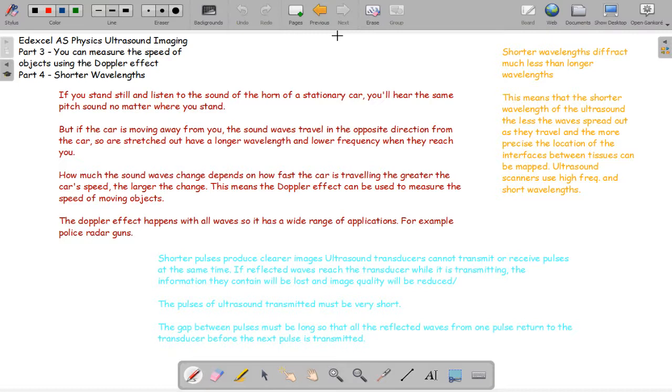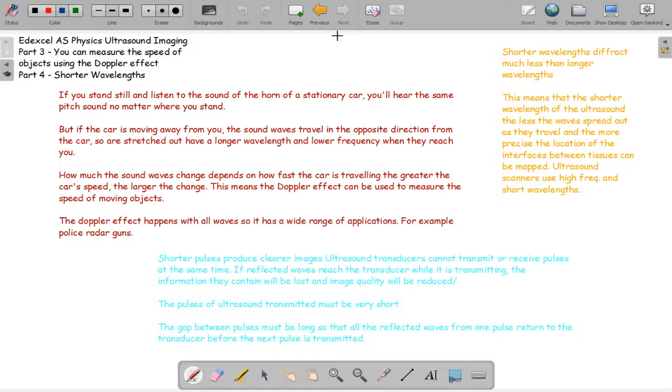Shorter pulses produce clearer images. The pulses of ultrasound transmitted must be very short, so that the reflections from nearby interfaces do not reach the transducer before the pulse has ended. The gap between the pulses must be long, like at least a millisecond, so that all the reflected waves from one pulse return to the transducer before the next pulse is transmitted.